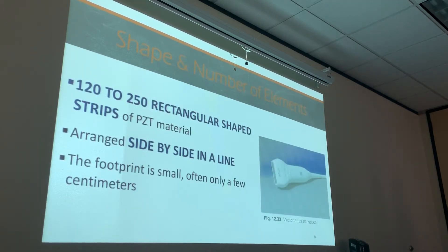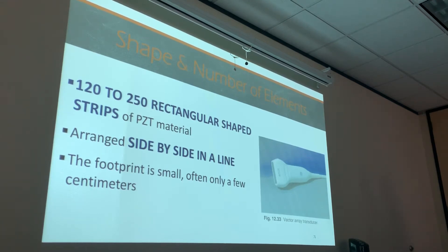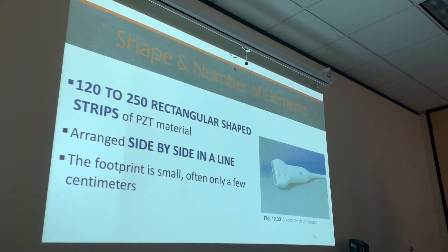It has 120 to 250 rectangular-shaped strips of PZT material, all arranged side-by-side in a line. Basically, all of our array transducers — except the annular array — are arranged side-by-side in a line, rectangular-shaped. The footprint is small, often only a few centimeters. It's not a very big transducer.